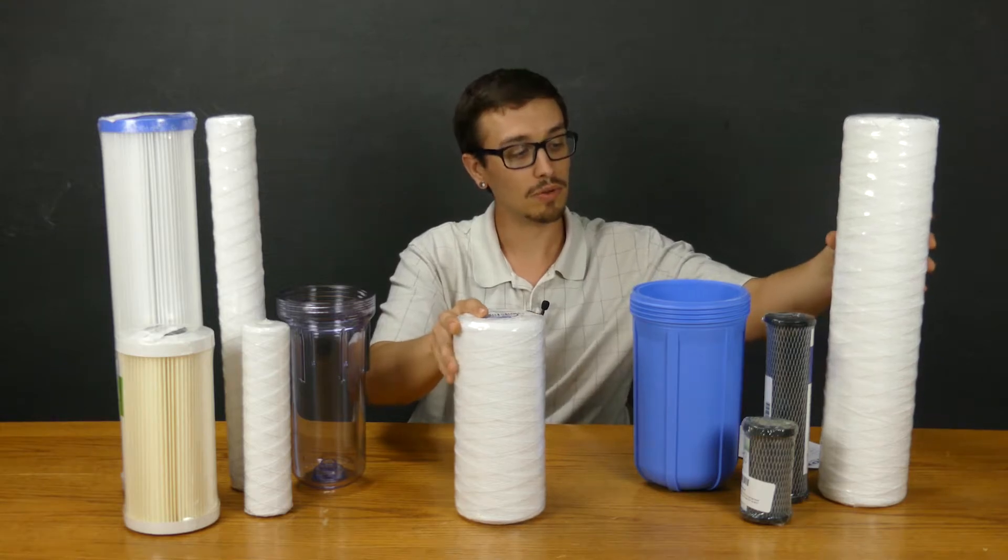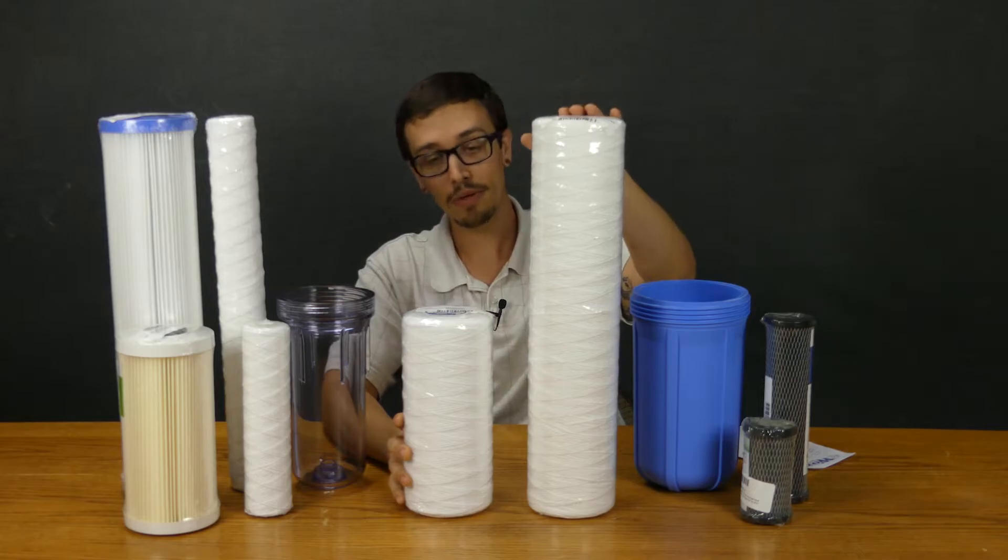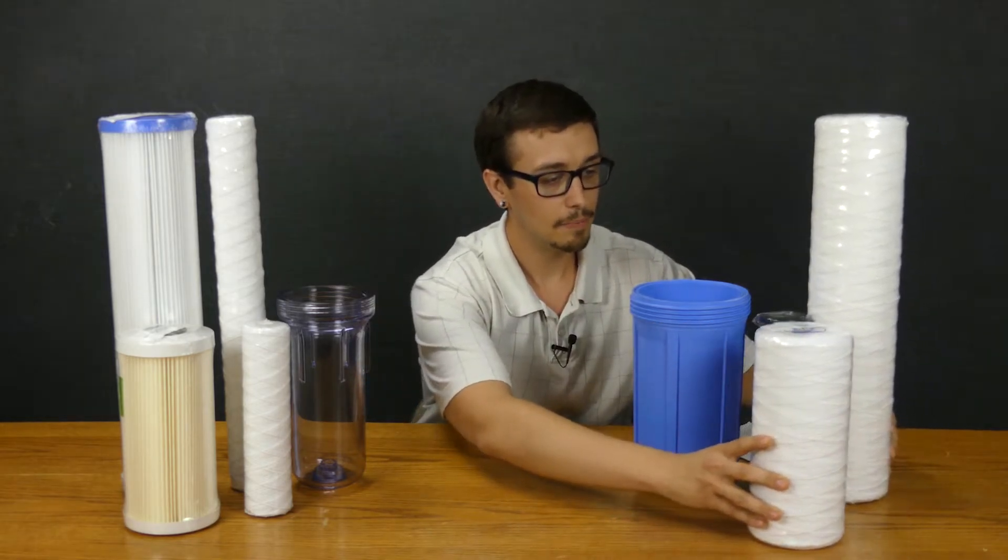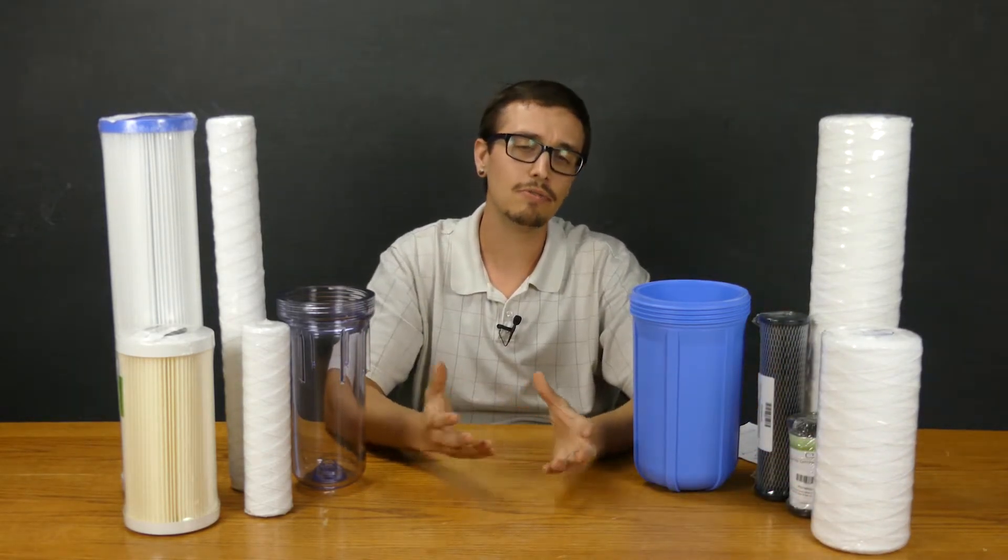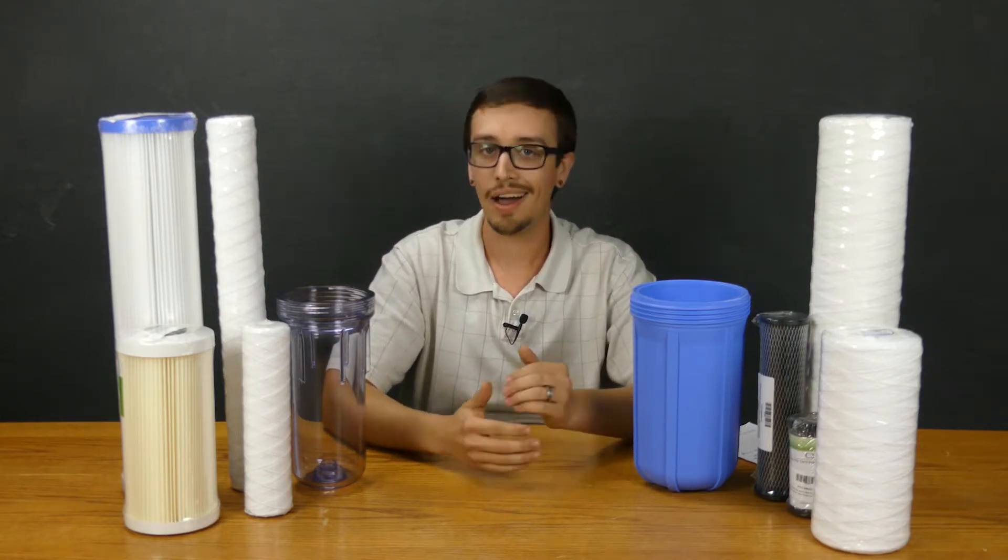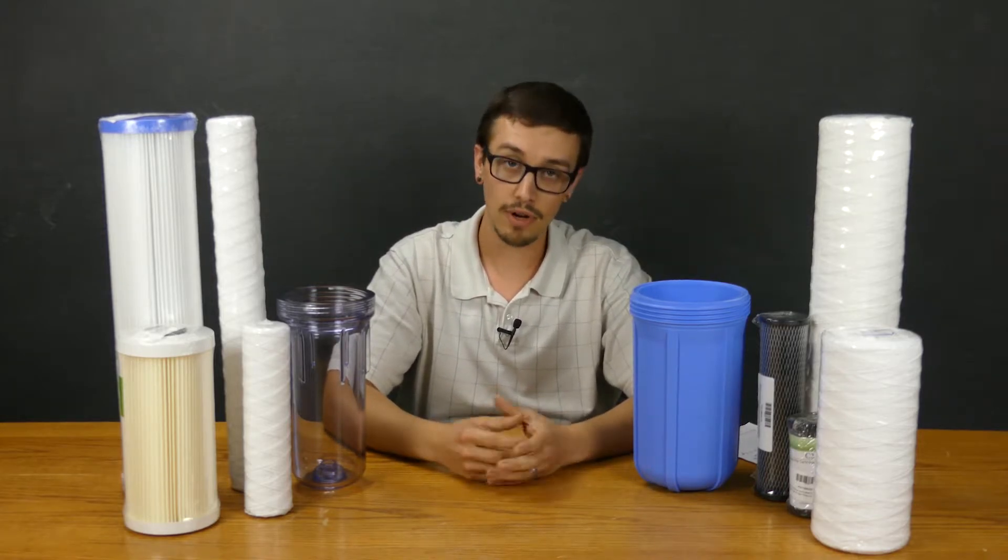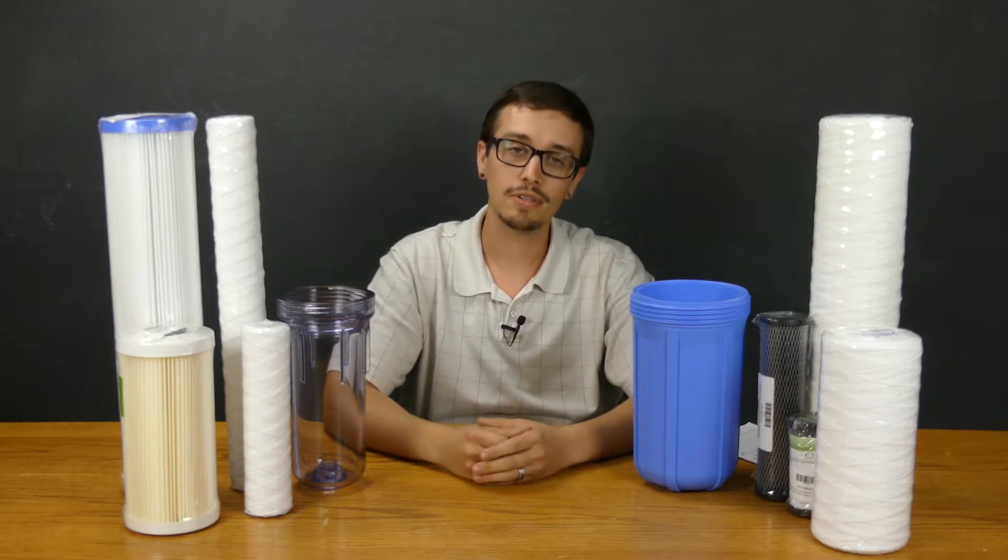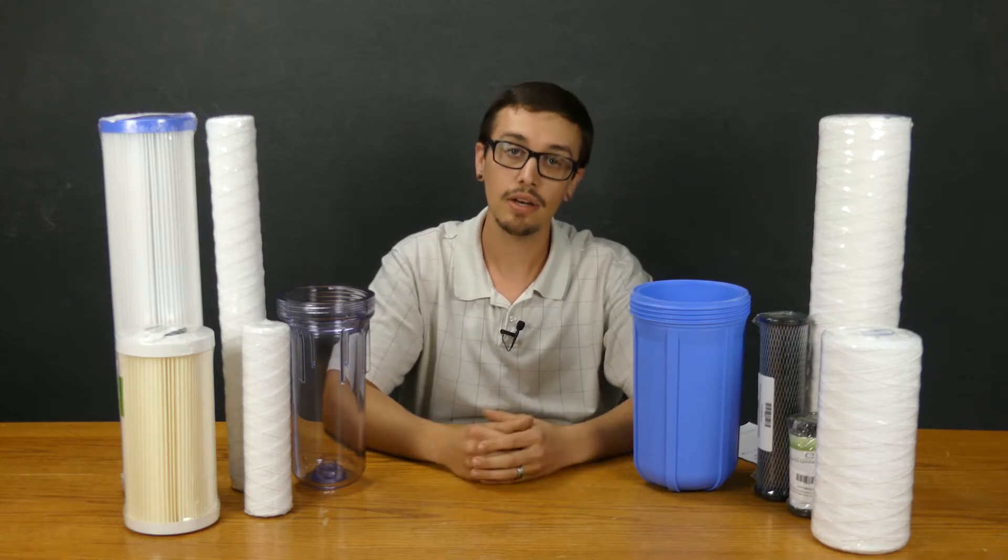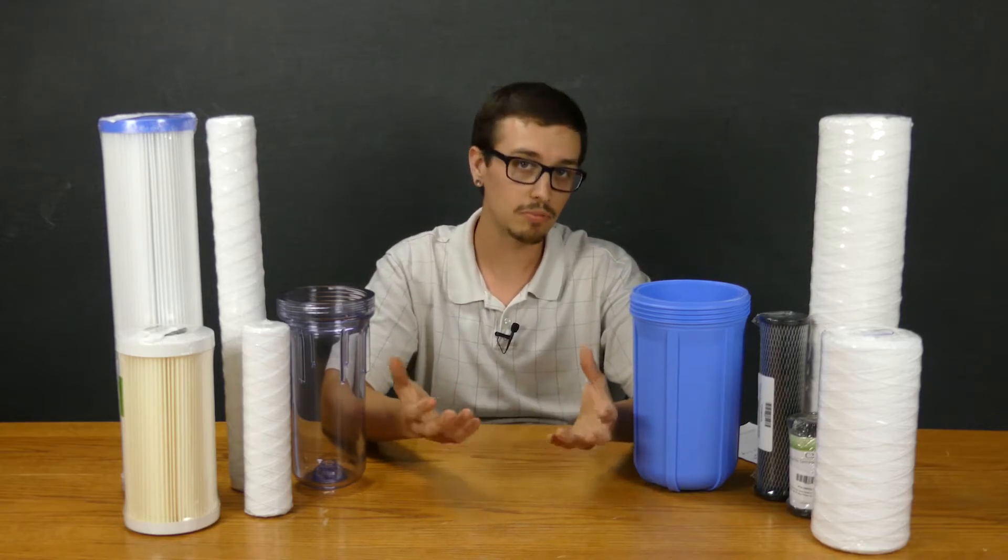The big difference between these two is size. This filter is essentially double the size of this filter. The difference in size is a characteristic of flow. If you have a higher flow system or a higher volume system, you're going to need a larger filter for a couple of reasons. First off, a larger filter is going to allow more water at one time through the filter. Secondly, a larger filter is going to have a greater capacity for holding things like sediment, debris, and buildup.